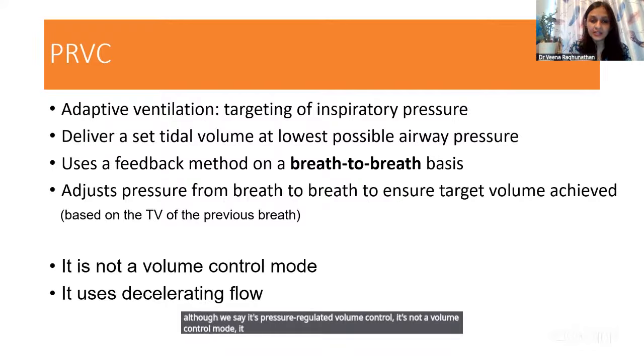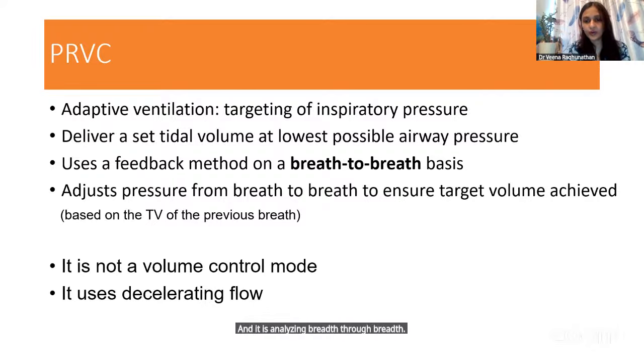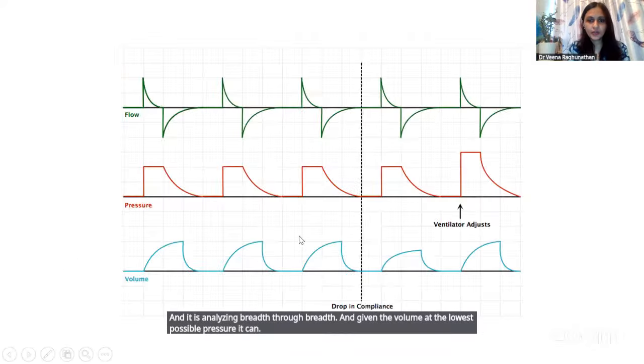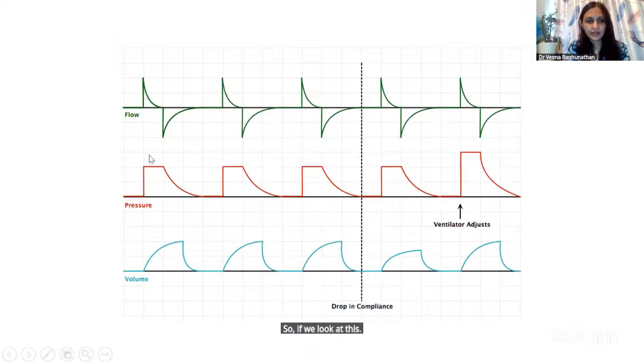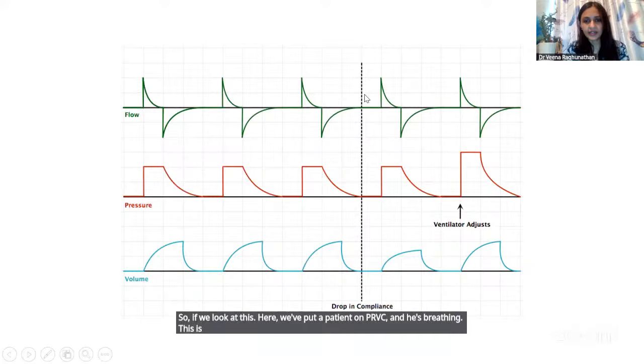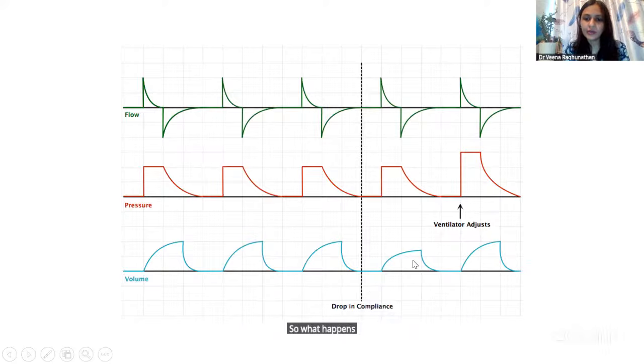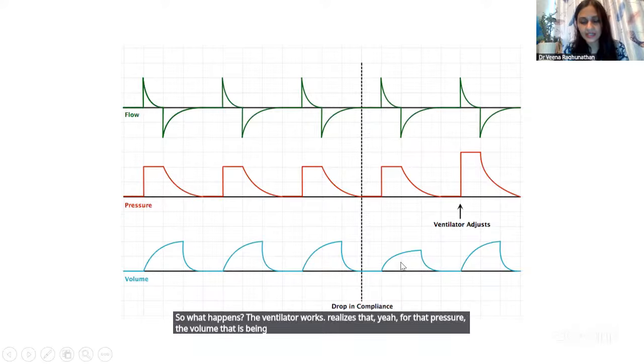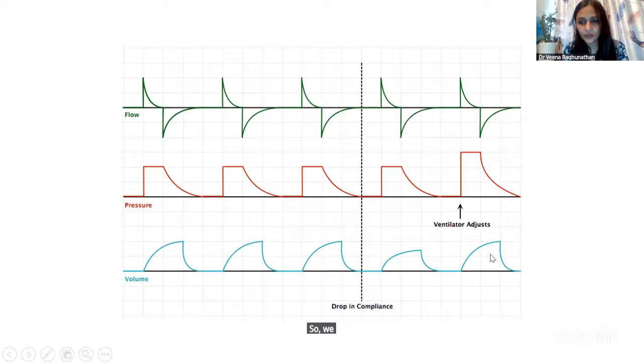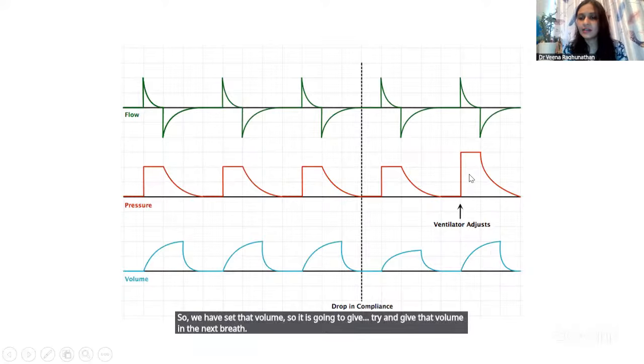It is using a decelerating flow and analyzing breath to breath, giving the volume at the lowest possible pressure it can. So if we look at this, here we've put a patient on PRVC and he's breathing. This is the ventilator graphic, and then there is a drop in the compliance. So what happens? The ventilator realizes that, for that pressure, the volume that is being given is less. So we have set that volume. So it is going to try and give that volume in the next breath at the cost of pressure.